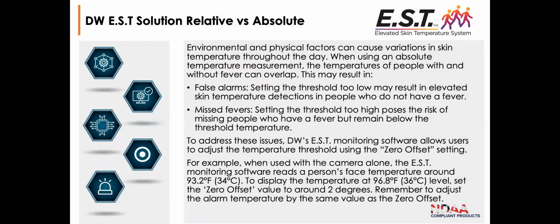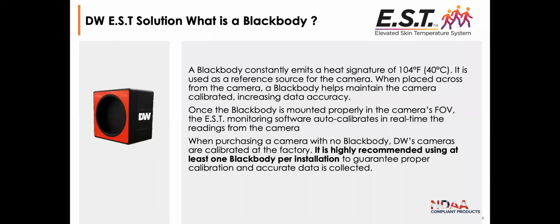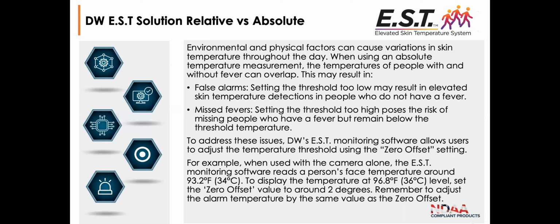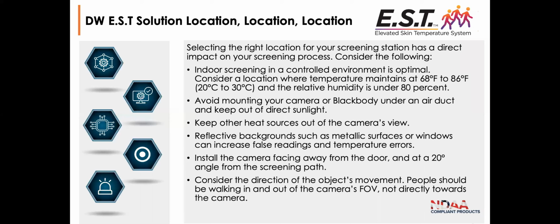One more thing I think I missed - it is highly recommended to use at least one black body per installation. We understand, and will show, that you can use this system without the black body; you can purchase the camera by itself. However, in terms of accuracy, you always want to use that black body. That's our recommendation with this particular product.